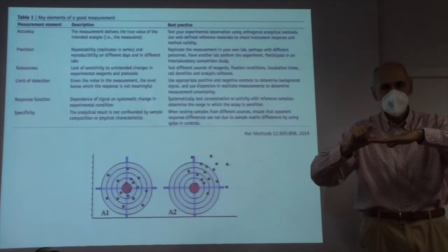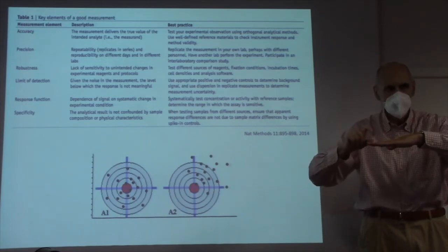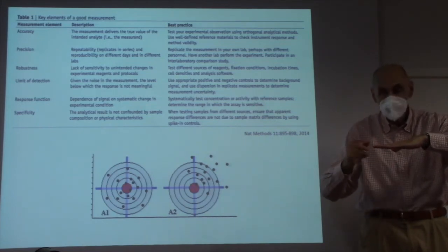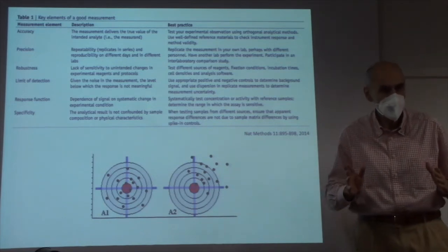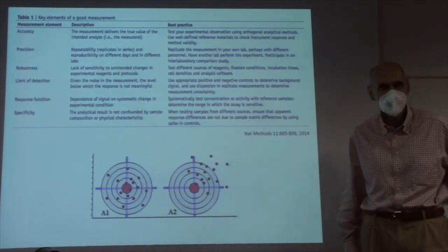A measure this high won't be significant because it's within the oscillation of the instrument. You don't really know whether this is pure noise or it contains a little bit of something you actually measure plus the noise in that precise instant. So you really don't know what to make of your measure. And there is no averaging in that case. It's really difficult to get a measure.